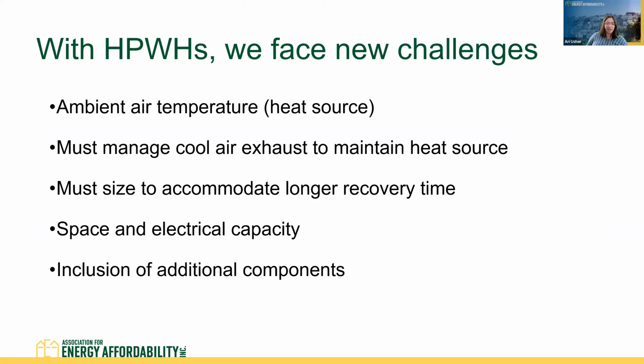Just in summary, with heat pump water heaters, we do face new challenges as this technology becomes more and more common. These will just be incorporated into our design. For the time being, ambient air temperature is the heat source, so we always need to consider the ambient air temperature for the install location. Heat pumps also exhaust cool air, so cool air exhaust needs to be managed to maintain the heat source, and that's done by including ventilation in designs. Storage tanks have to be sized to accommodate longer recovery time. And then there are space and electrical capacity considerations, and the additional elements as I mentioned: the mixing valves, sometimes electric resistance trim heating or backup, and sometimes swing tanks.